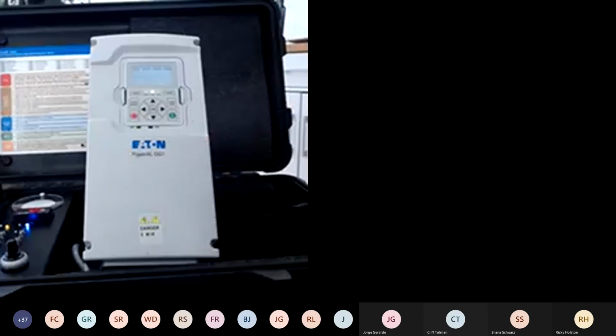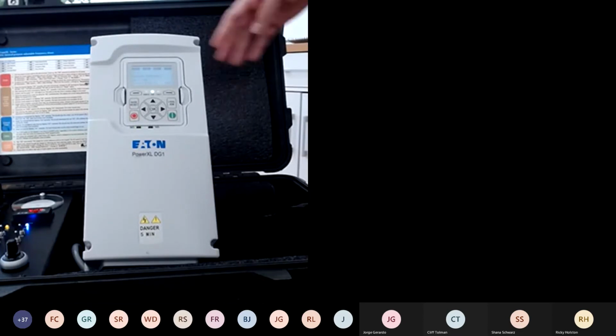So there are a lot of neat benefits here. You have your safe torque off, you have your IOs, so you can add pilot lights, switches, buttons, extra safeties. You can add a bypass. The VFD that I show here does not have a bypass, but you can do a 3-contactor bypass, or a soft start bypass, or a redundant VFD bypass for critical applications. So you can have one drive as master, a secondary drive as slave, and operate your system in critical applications when one fails and have the other take over.